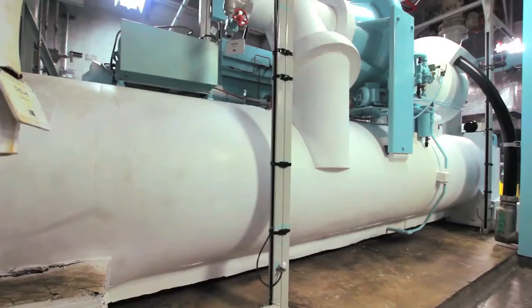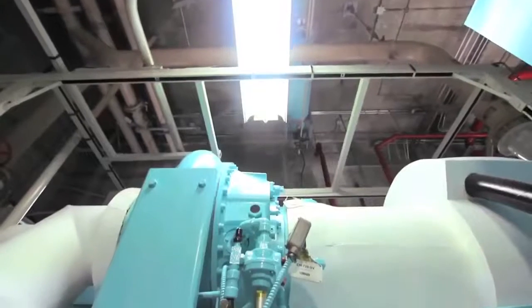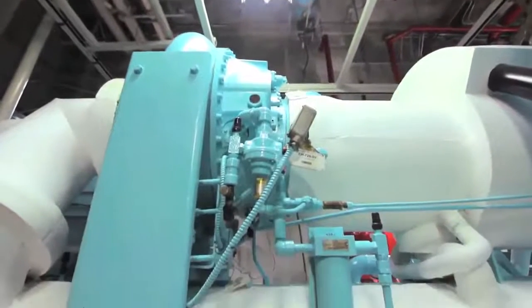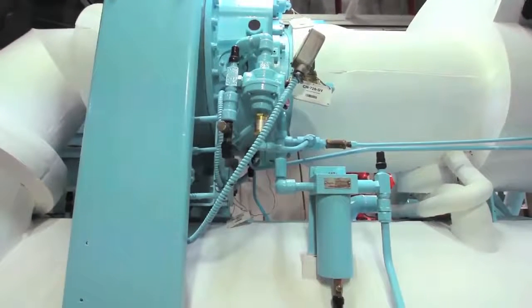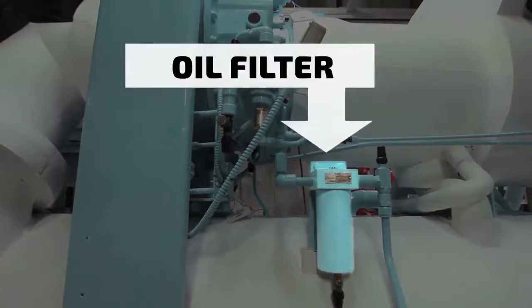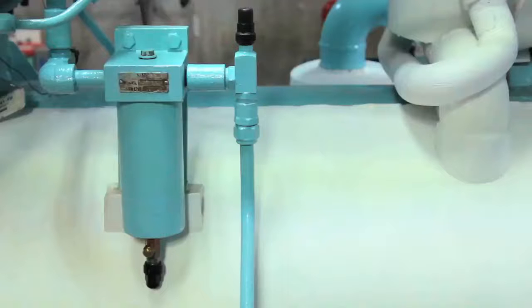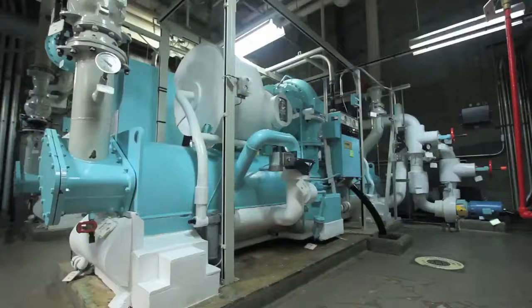We have 2 pumps within the compressor itself. These are small volume, high pressure pumps driven off the shafts of operating components. These maintain stable pressure during operation. There is an oil filter that purifies oil during operation. It's also one of the filters you'll need to take care of on your periodic maintenance. We will discuss periodic maintenance and the potential pitfalls in a later section.